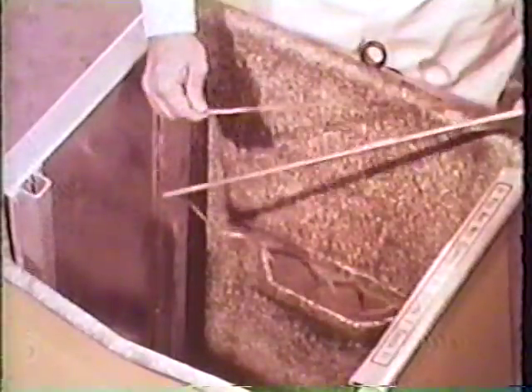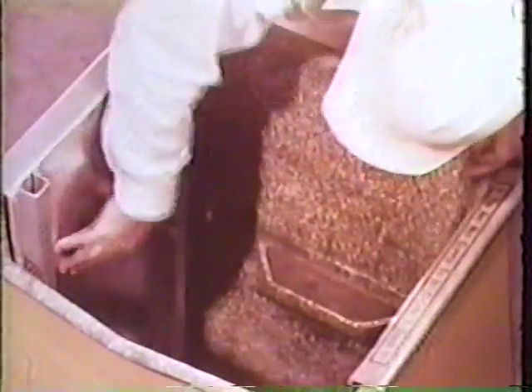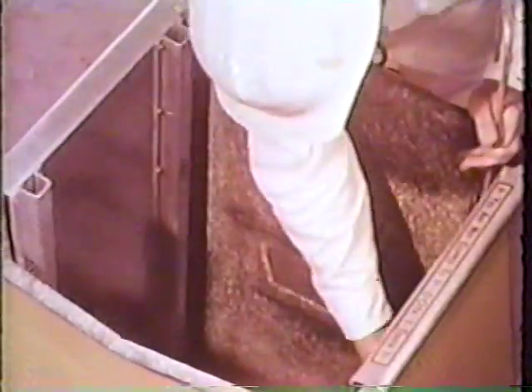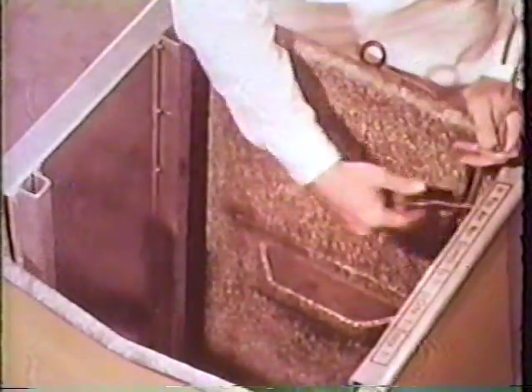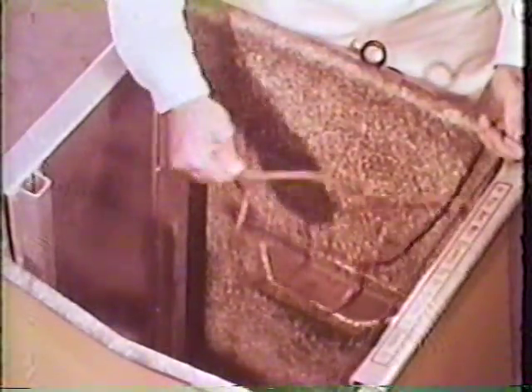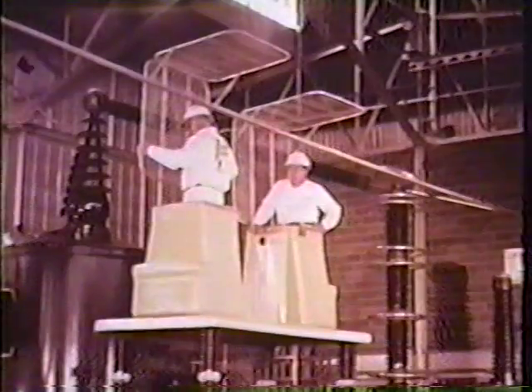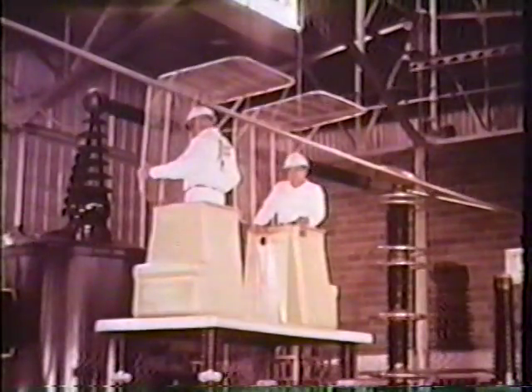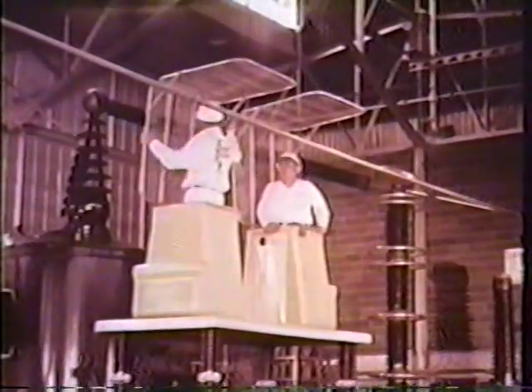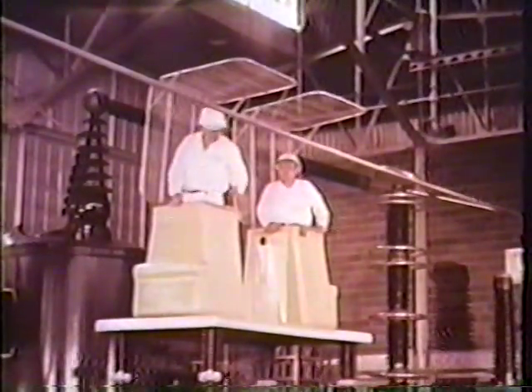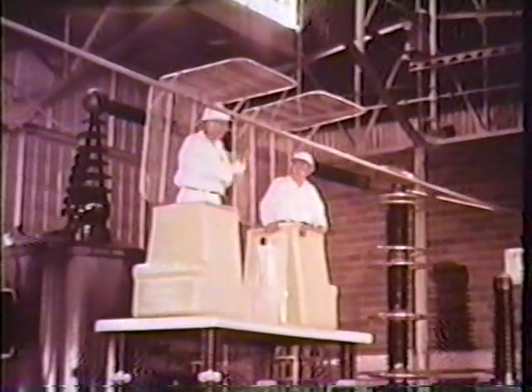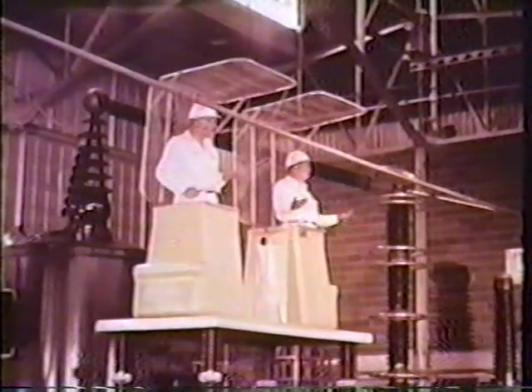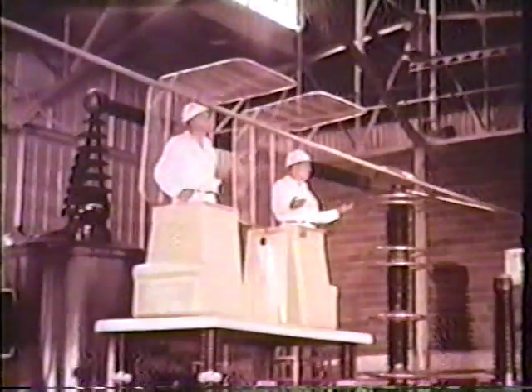By an application of the Faraday cage principle, these engineers proved that a man standing in a metal-lined bucket can bond it to an energized conductor without shock or discomfort if the bucket is insulated from ground. This bucket shielding is comfortable up to about 230 kV. At higher voltages, additional shielding can easily be attached to provide comfortable working conditions. Conductive sole shoes bond the men to their shielding, so both are always at the same potential.